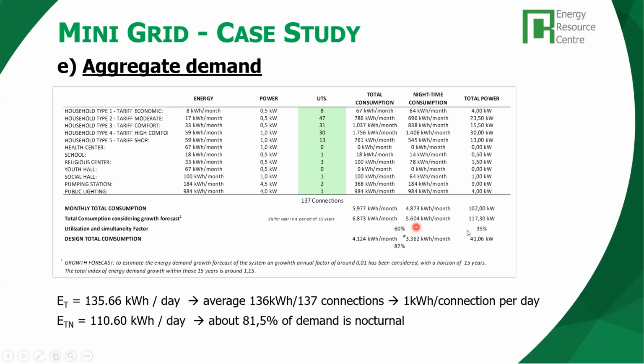Then we apply our use factors and our simultaneity factors so that we can minimize the total design consumption, the demand we use for the design of the mini grid. And these are the final values that we will use, which is 4,124 kilowatt hour per month, which is equivalent to 136 kilowatt hour per day. And the nocturnal fraction, the nighttime, is 3,362 kilowatt hour per month, which is equivalent on average to 111 kilowatt hour per day. Okay, our net power demand because of the simultaneity factor comes down to 41 kilowatt power demand. Okay, that's at the peak.